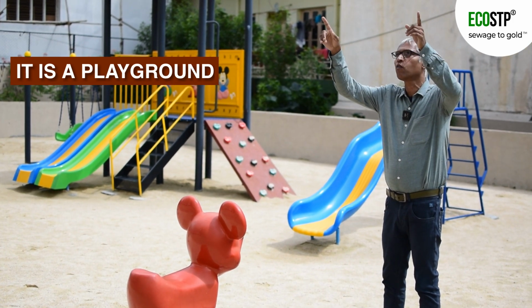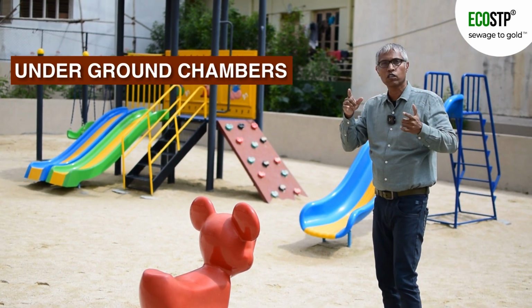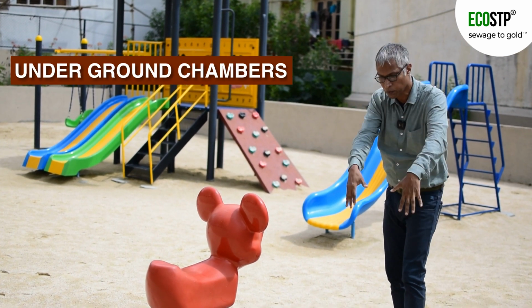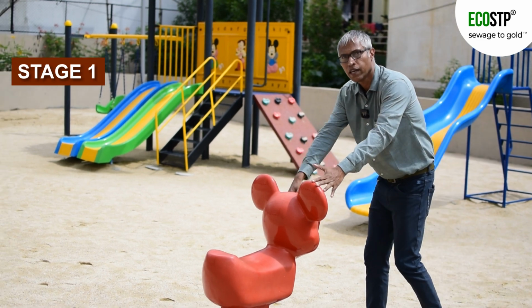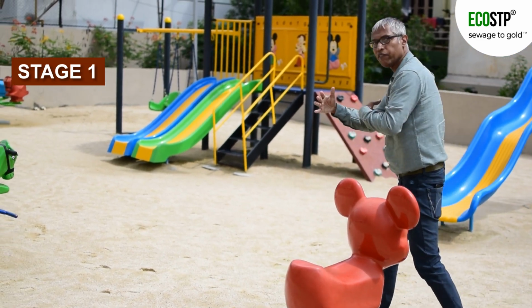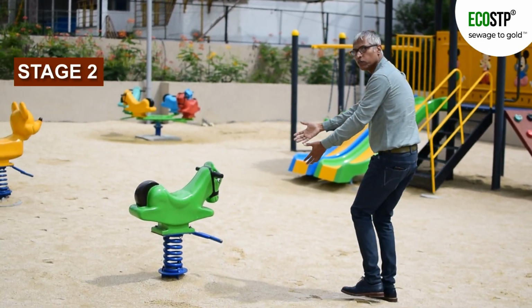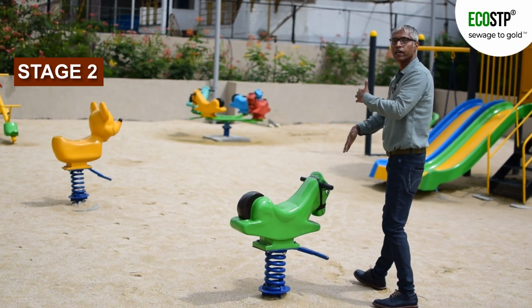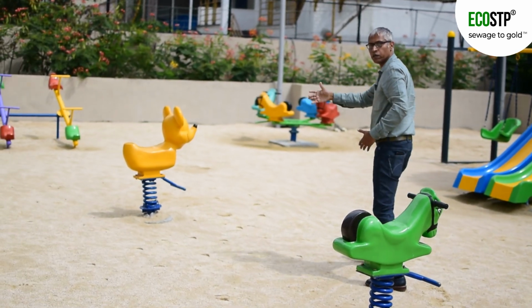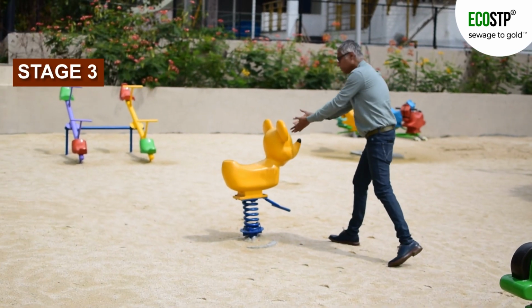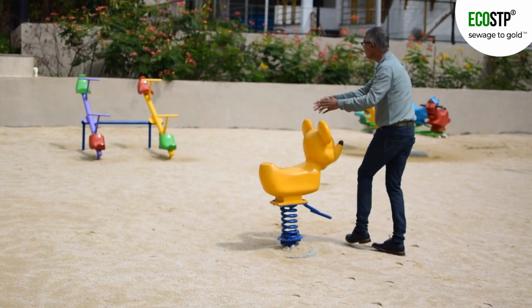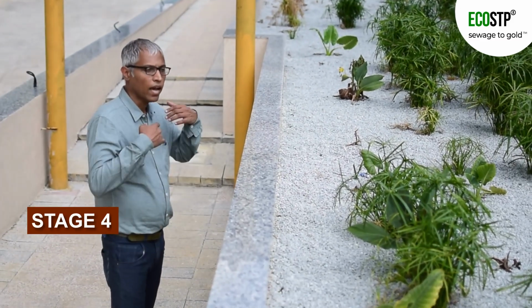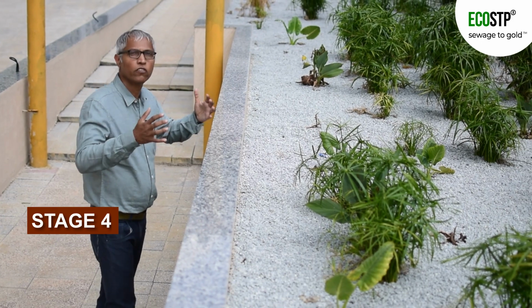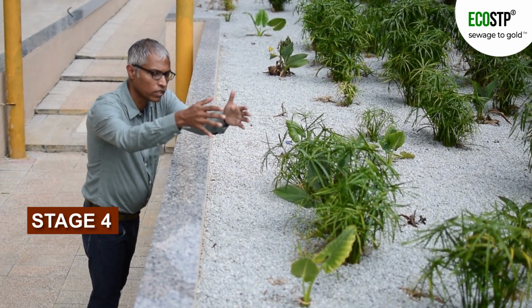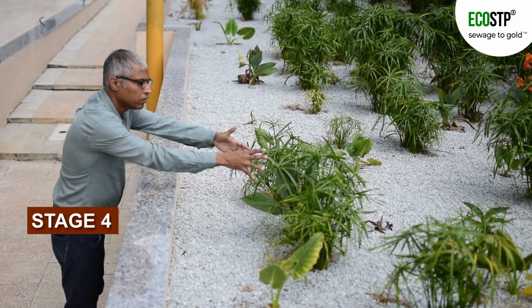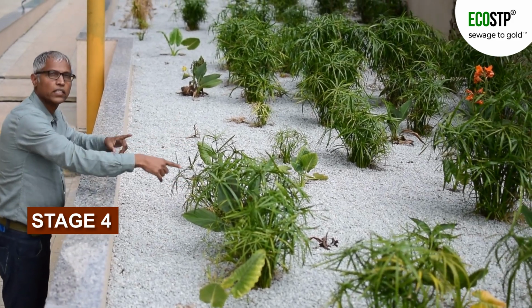So whatever they flush down in this building, grey water, black water, washing machine waste, everything comes below the tanks, below, comes here and gets treated. And then by gravity, it moves to the stage 2 below this. And again by gravity, goes to multiple chambers, moves to stage 3, the yellow Mickey. And then we move to stage 4. And in stage 4, we have plant biofilter, PBF. The water flows through the gravel, and we have 3 types of plants, Canna, Colocasia, Papyrus.